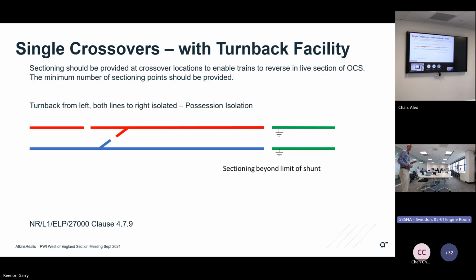However, if you have got a turn-back facility - so let's say you want to run trains from the blue track over the crossover onto the red track, driver goes to the other end of the train and heads back, which you typically find near stations - then it changes a bit. Then, as well as still providing a section break here and here so you can work around a fault on the blue, you also need to provide a section break here, so that if you need a possession isolation of everything north, you still retain the ability to use the turn-back facility for electric trains.